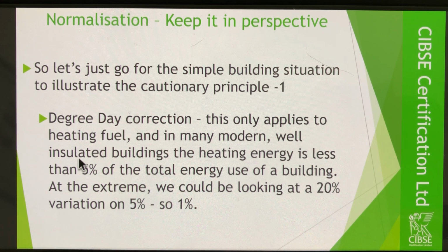In some manufacturing installations, there's a lot of heat that is unavoidably lost from the manufacturing process, which is heating the manufacturing facility, and very rarely is the heating needed to top up on that. So again, the effect of the outside weather doesn't really have much effect on the heating energy because there isn't very much in that sort of building. So a lot of the time it is, but don't assume. Have a look at the data. And if your heating consumption isn't changing between March to June to October to December, then it's not a relevant variable.